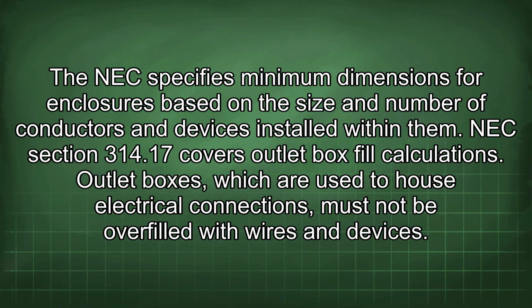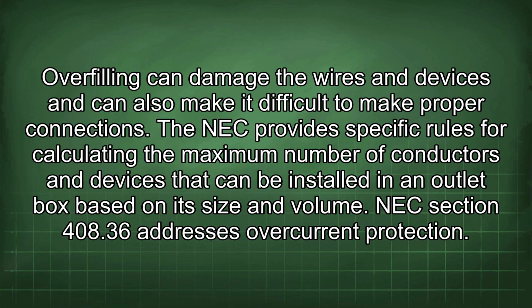NEC Section 314.17 covers outlet box fill calculations. Outlet boxes, which are used to house electrical connections, must not be overfilled with wires and devices. Overfilling can damage the wires and devices and can also make it difficult to make proper connections. The NEC provides specific rules for calculating the maximum number of conductors and devices that can be installed in an outlet box based on its size and volume.